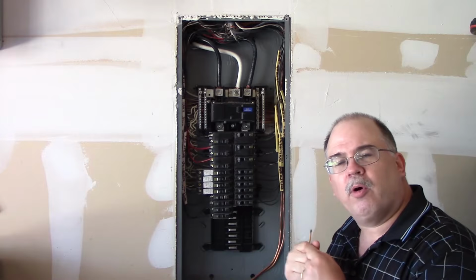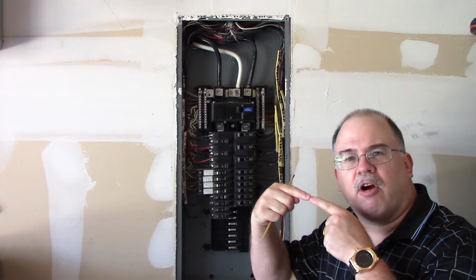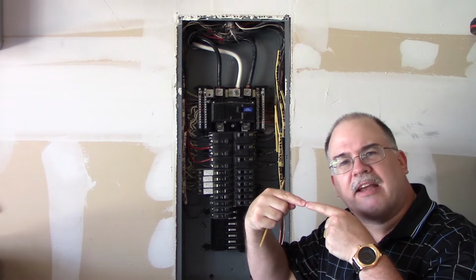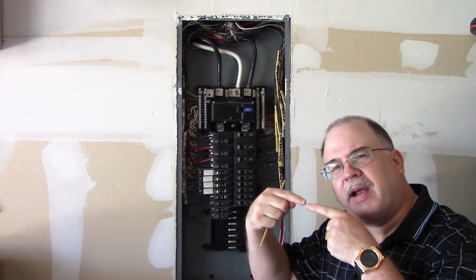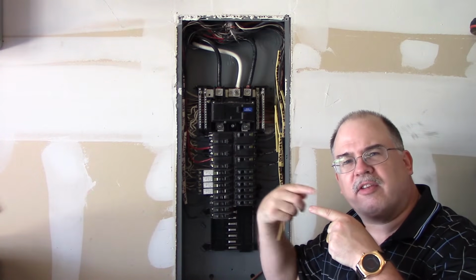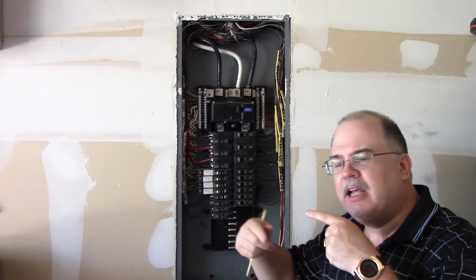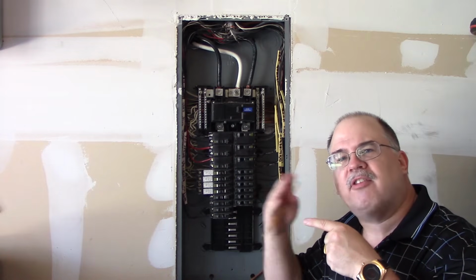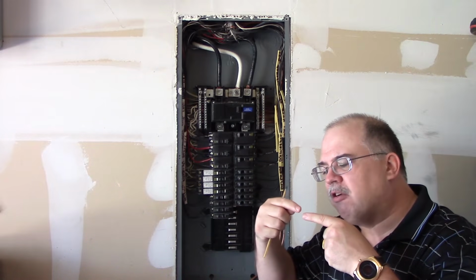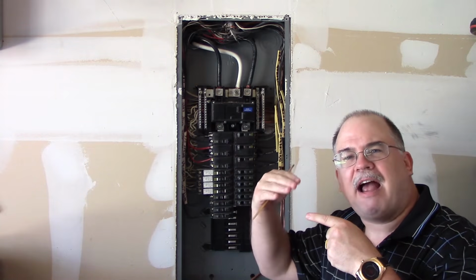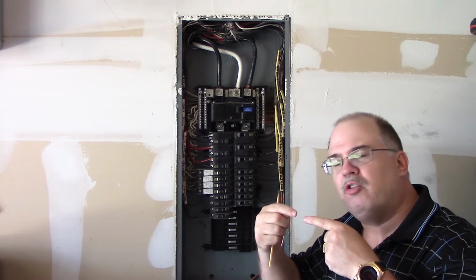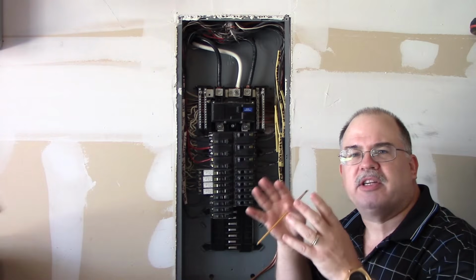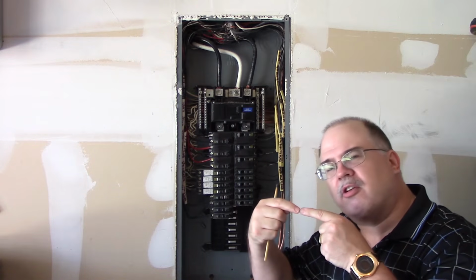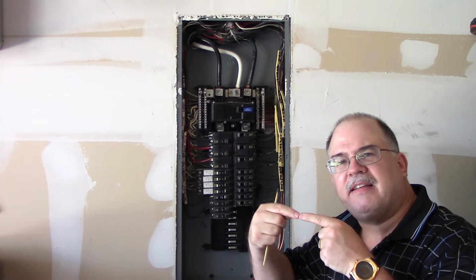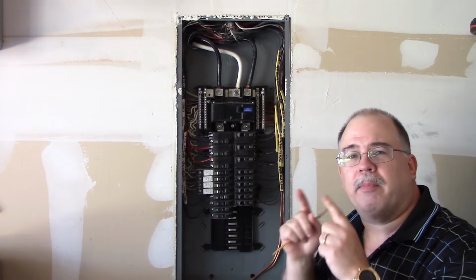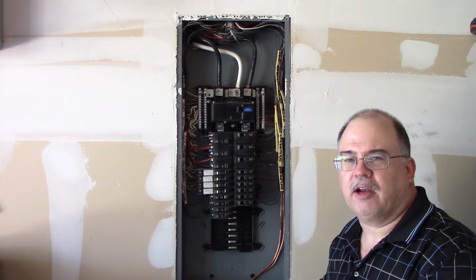The other one it looks for is called a series arc. And that is where you have a loose connection, where it's just barely connected, and you put a load on the system because it's very load dependent. You plug something into the circuit and it creates a load through the system, and then it creates an arc right here. And this arc can rise in heat over time to the point where it can cause pyrolyzation of material and cause a fire. So this little series arc is what's being detected by a combination. So it's the parallels and the series that are being detected.